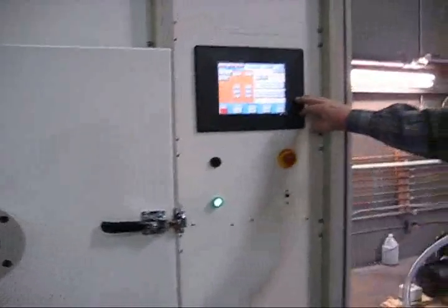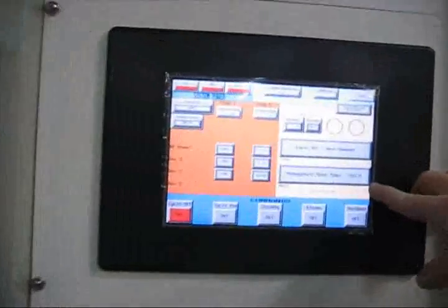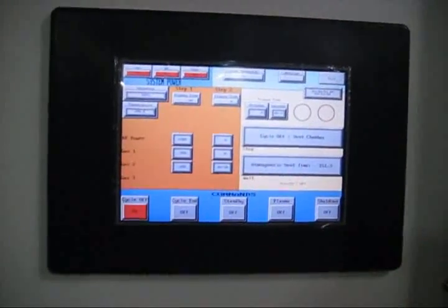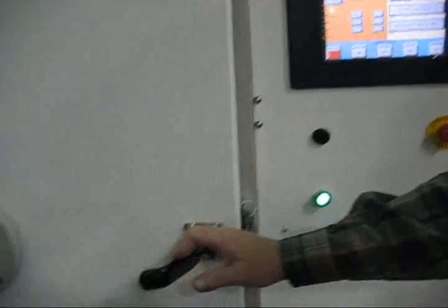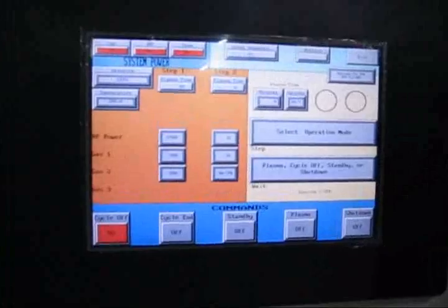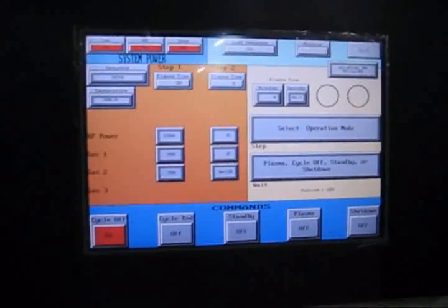All right, back around the front here. We're venting the chamber. It has an atmospheric vent timer. Typically, we set that for a longer period of time than it takes to actually open the door. But as you can see, once you open the door, the timer zeros out. Okay, that's good.